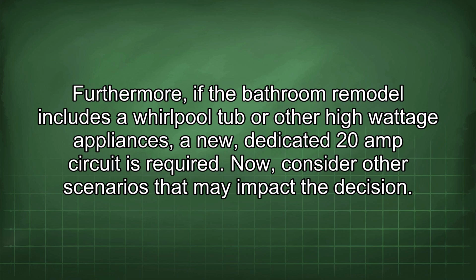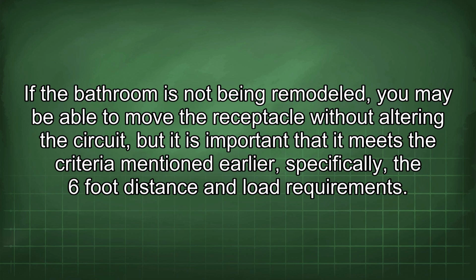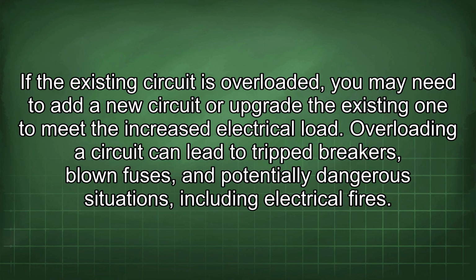Now consider other scenarios that may impact the decision. If the bathroom is not being remodeled, you may be able to move the receptacle without altering the circuit, but it is important that it meets the criteria mentioned earlier, specifically the 6-foot distance and load requirements. If the existing circuit is overloaded, you may need to add a new circuit or upgrade the existing one to meet the increased electrical load.